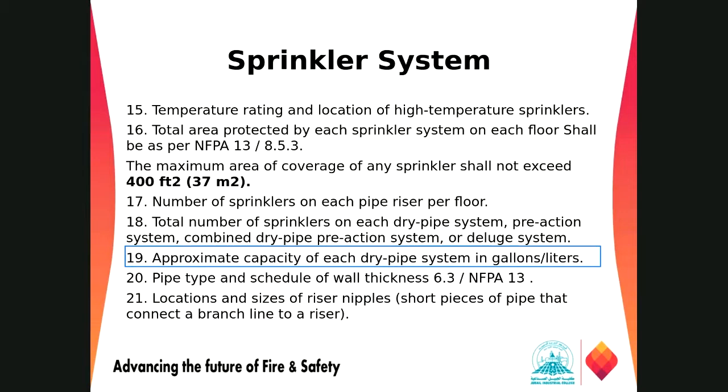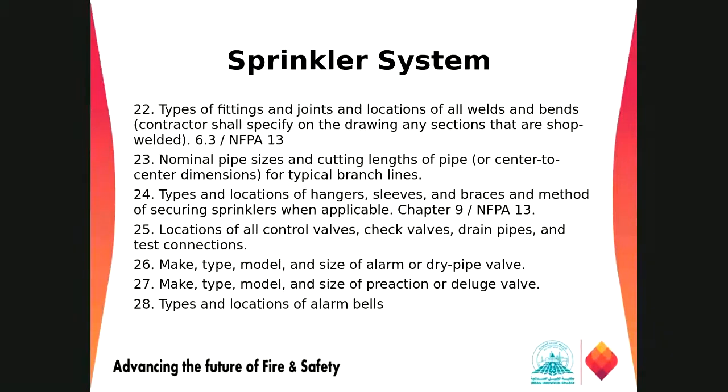Then look for the pipe types, the material of construction, the thickness, schedule of that one as per 6.3 of NFPA 13, right? Look for the location and sizes of the riser nipples. Then look for the fittings, the types of the fittings and all requirements, the hangers location, the listing or the approval of those hangers as per chapter 9 of NFPA 13, right? Then look for the location of the control valves, check valve, drain pipings, and the test connections, right?